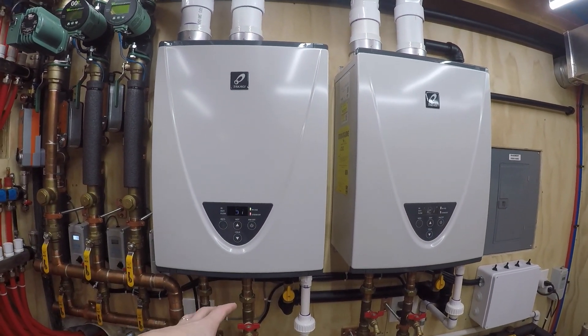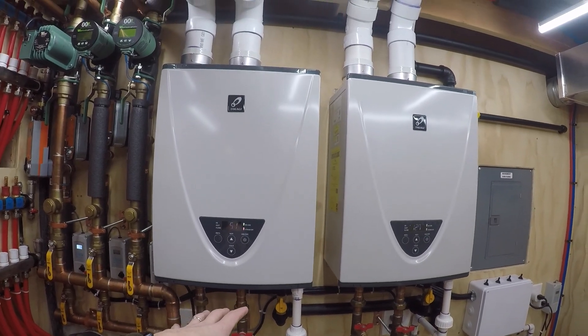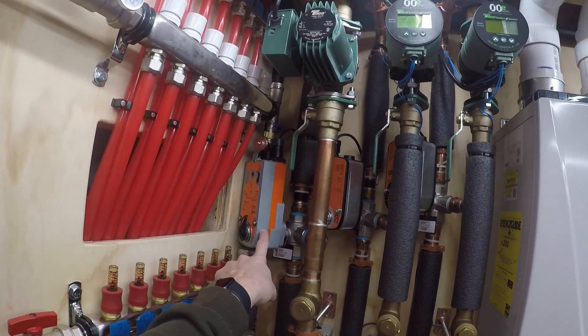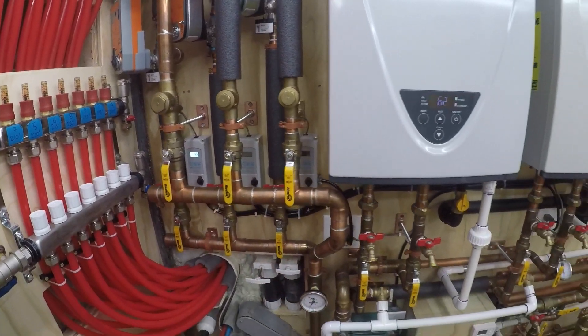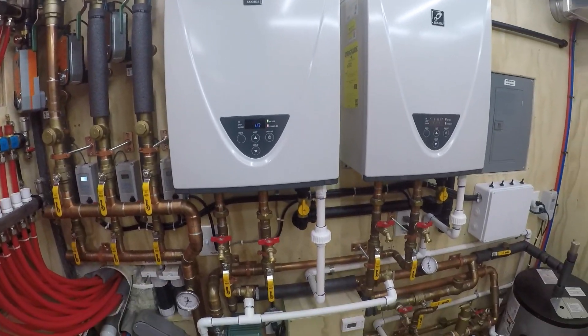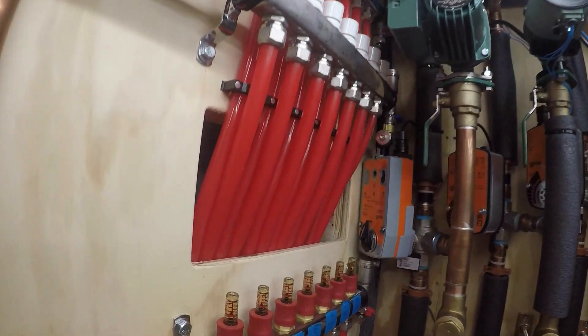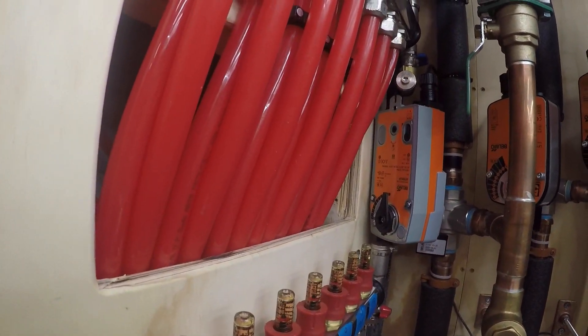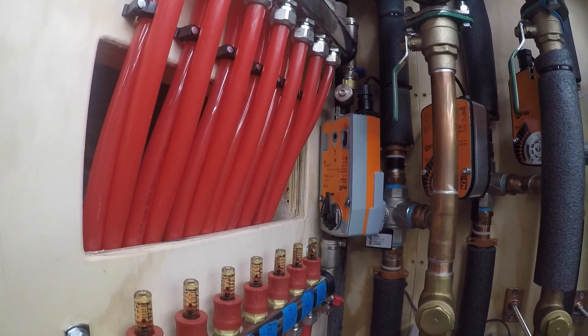This is total BTU usage for both units. Right now each unit is pulling about 50,000, so you're getting 99,000 total. The reason it's actually dropping is because it's just circulating the primary loop right now — this valve is still opening, so that ice-cold glycol has not had a chance to fully get pumped back through the heat exchanger yet. Now you'll start to see it climb because that valve is almost completely open.